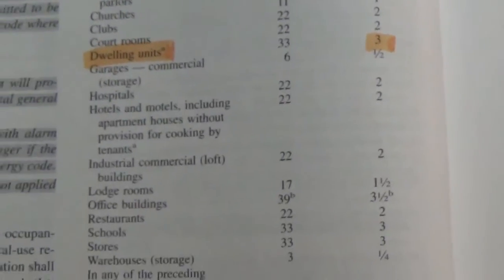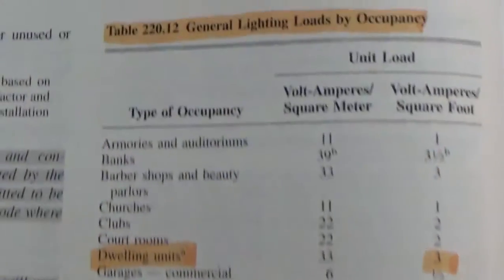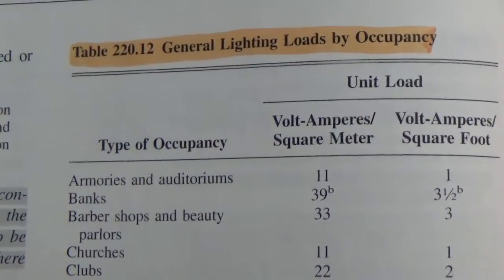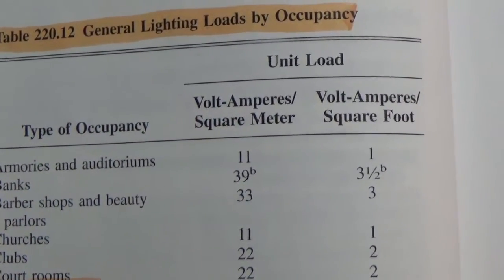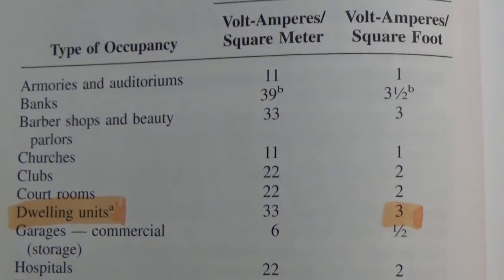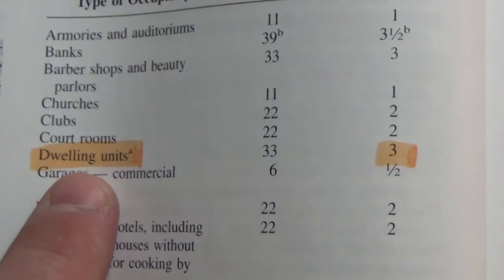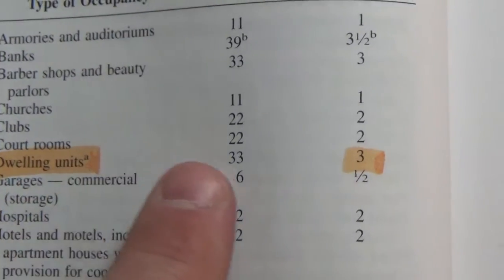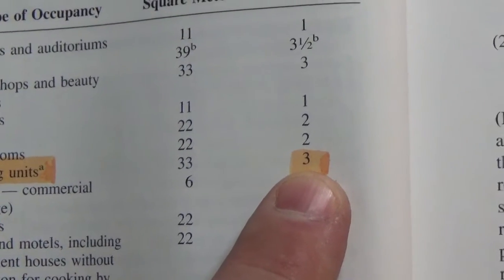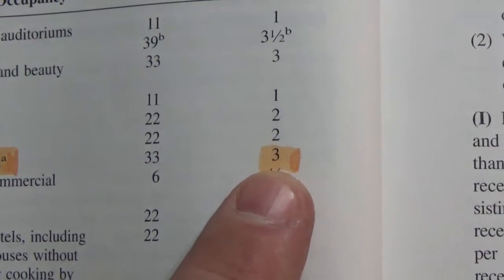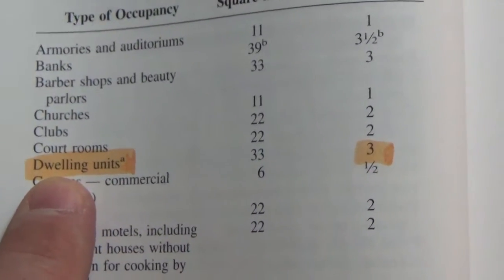It gives us a whole list of different occupancies. What we're looking at is volt amps per square meter and volt amps per square foot. We're going to focus on the per square foot. So we're going to go down and find dwelling, and the dwelling unit we follow all the way over. We're going to multiply our square footage by 3. 3 VA is the number that we use for a dwelling unit.